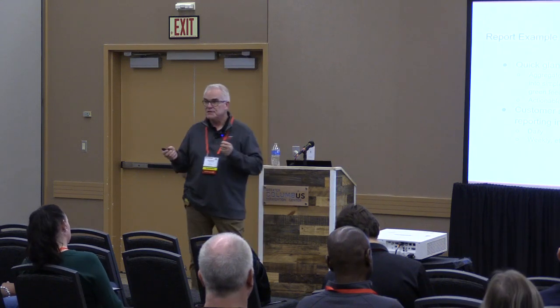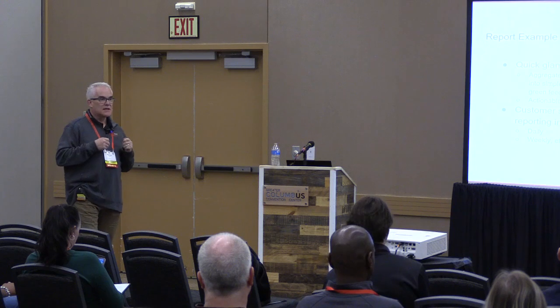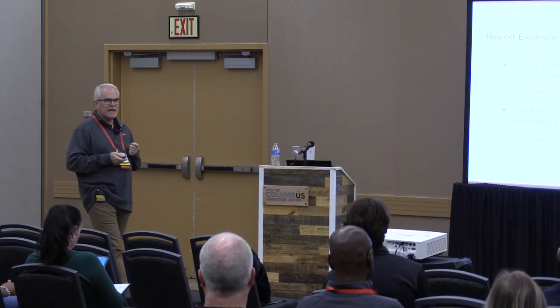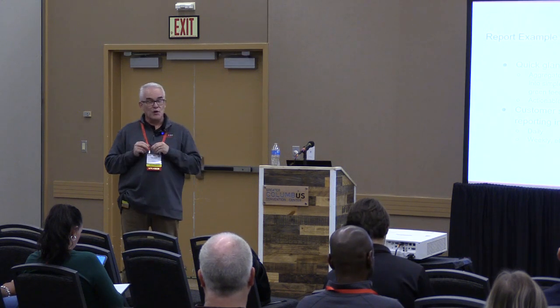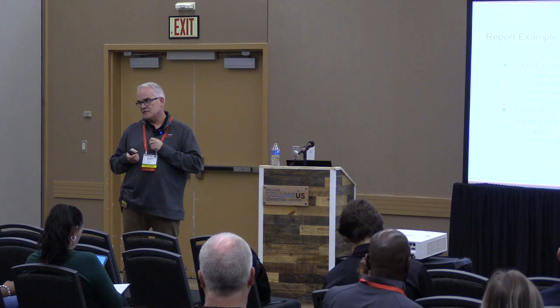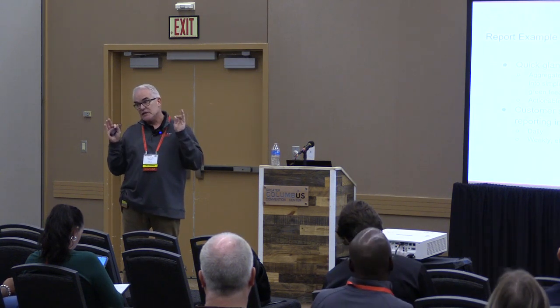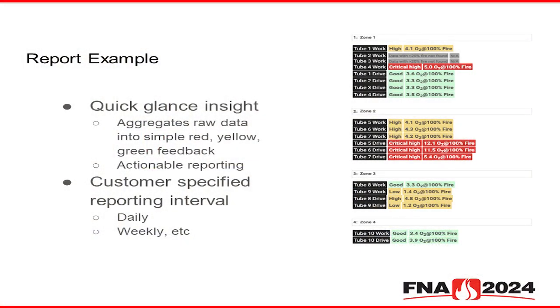We have a customer that has this system on 3 continuous annealing furnaces, 48 burners per furnace. They used to always be out of tune. Their maintenance lead now, on Monday morning, gets a report, and he has every burner in green in about 20 minutes. So all of us are shorthanded on staff.